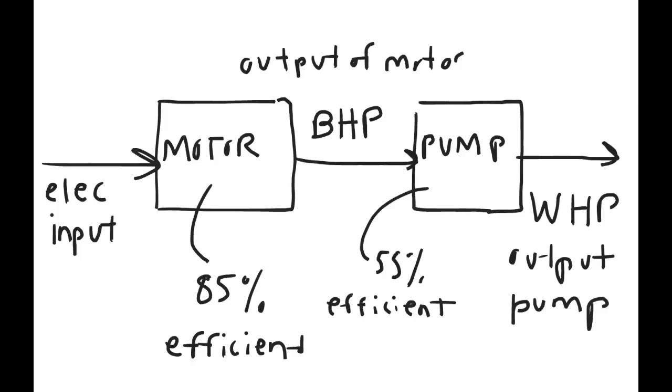And just to recap, always remember that the efficiency of the system is always the output divided by the input. So if you wanted to find the input to a pump, you take the efficiency and the water horsepower, which is the output. Or if you wanted to find the input to the motor, you would take the efficiency and the output of the motor and do it algebraically to find the answer.